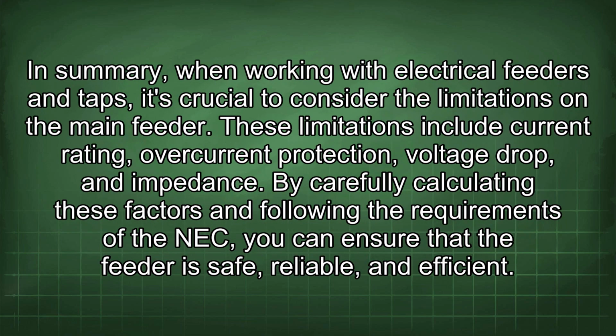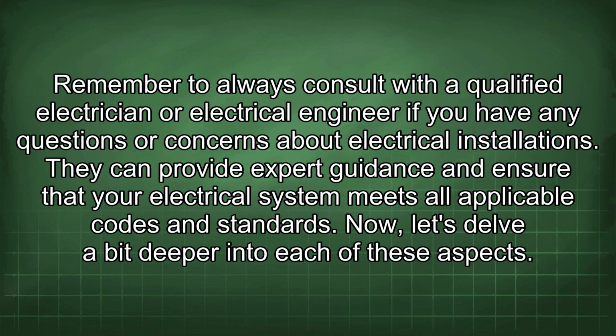In summary, when working with electrical feeders and taps, it's crucial to consider the limitations on the main feeder. These limitations include current rating, overcurrent protection, voltage drop, and impedance. By carefully calculating these factors and following the requirements of the NEC, you can ensure that the feeder is safe, reliable, and efficient. Remember to always consult with a qualified electrician or electrical engineer if you have any questions or concerns about electrical installations.